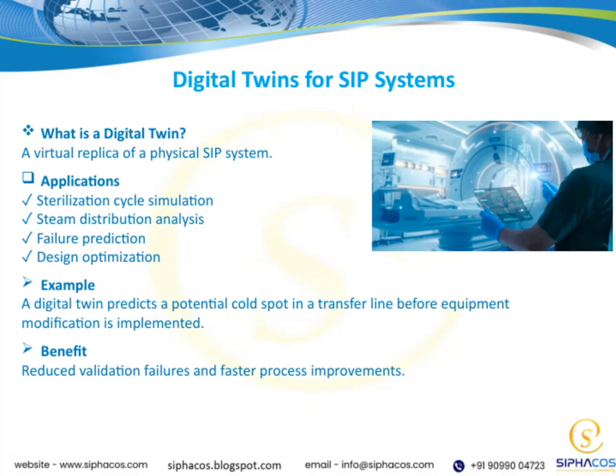Let's talk about digital twins for SIP systems. A digital twin is basically a virtual copy of a real, physical system — in this case, a sterilize-in-place setup. We use these twins to simulate sterilization cycles, analyze steam distribution, predict failures, and optimize design. For example, a digital twin can spot a cold spot in a transfer line before any changes are made to the equipment. This means fewer validation failures and quicker improvements in the process. It's like having a crystal ball for system performance.